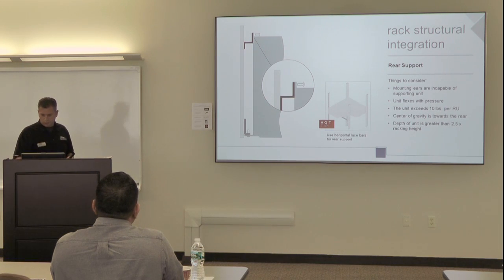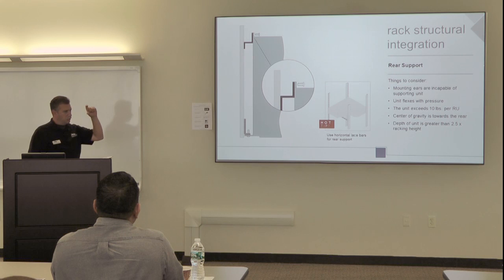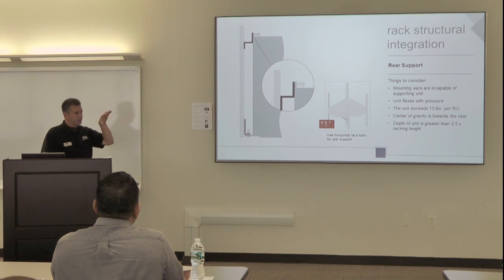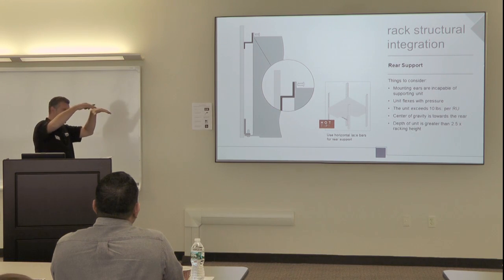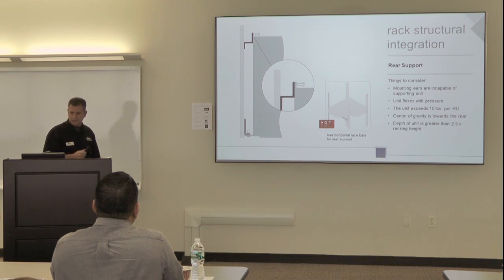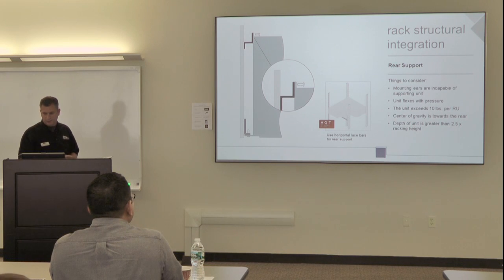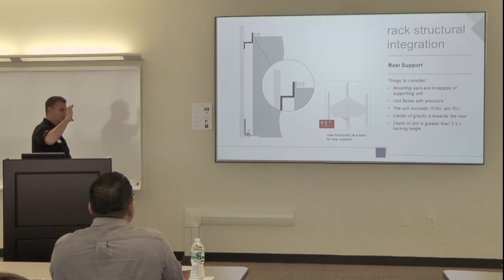A couple of things to think about: roughly 10 pounds per rack space, so a 2 rack space unit around 20 pounds should be okay, but you also need to look at where the center of gravity is. Some equipment has more weight toward the back, which can make it want to dive down. Also consider depth, about 2.5 times the rack height — you might have a 4-space piece that sticks out pretty far in back without rear support.